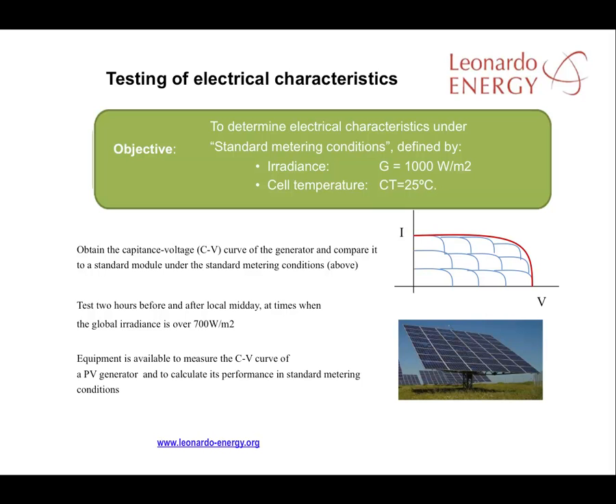Nowadays there's a lot of equipment that can help you obtain this curve and translate it into standard conditions. This test has to be done two hours before and after local midday. Before the test is carried out, the global irradiance has to be at least 700 watts per meter squared.